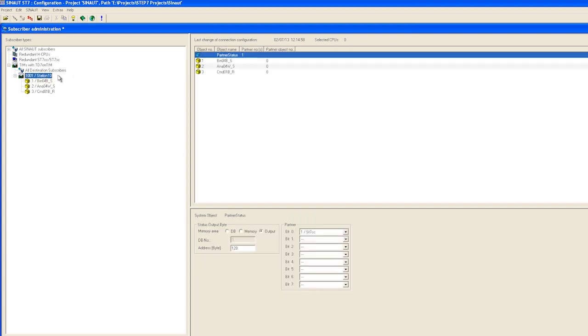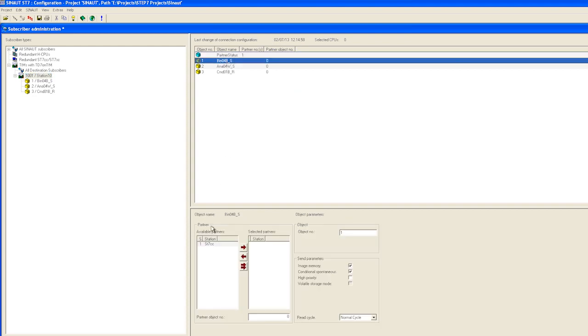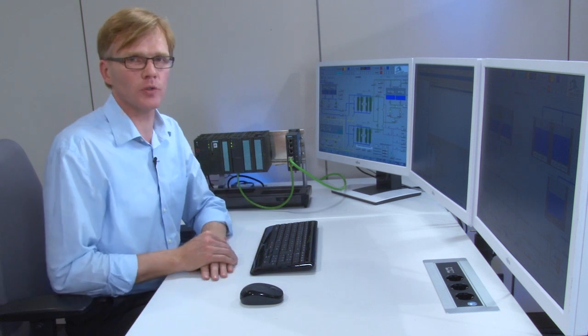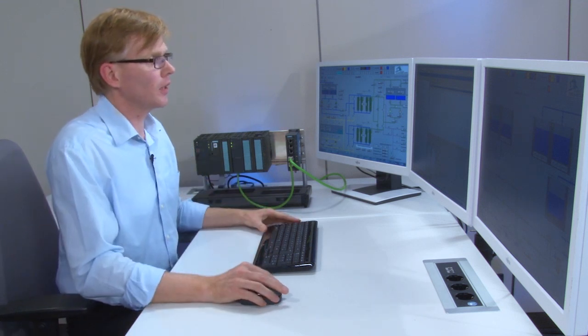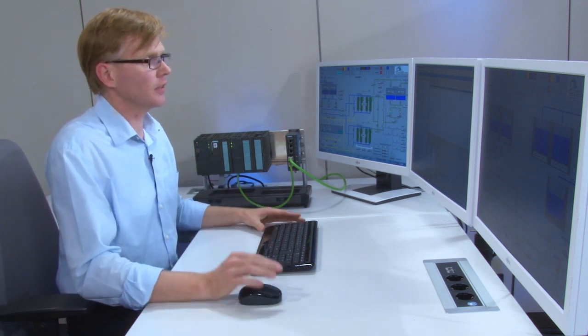Then we configure the partner station to which the object will be sent. This is our ST7 CC with control center number 1. If needed, the object number can be adapted. In our case we will use the default assignment. The default method for transmitting the objects is called image memory method. This means that only the values that are present when the connection is active are transmitted. Intermediate values are lost.